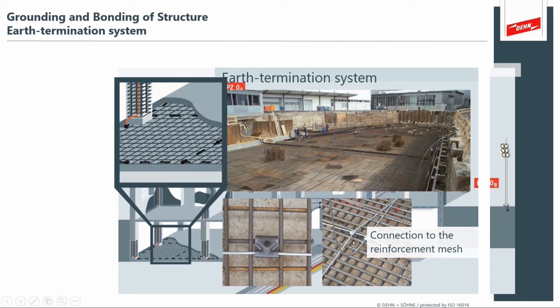If you've seen a lot of rebar installations, you might notice that a lot of times the rebar is only tied together with wire hangers. And that is not necessarily a connection that's for the purpose. And so that's why it's really important to have exothermic welded joints and connected systems that are rated and designed for the actual connection to the reinforcement of the mesh.